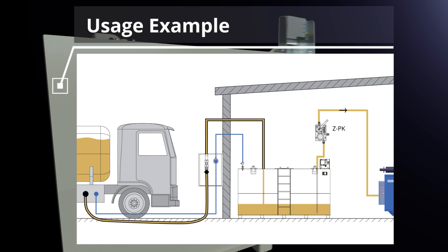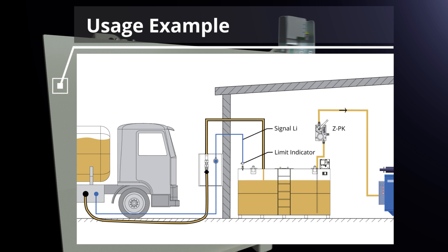When the maximum fill level is reached, the tank truck pump is automatically switched off by the limit indicator via the signal line. This prevents the tank from overfilling.